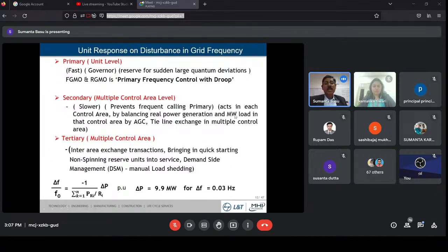So how can a very small frequency change demand a small incremental power? If there is a 0.03 hertz frequency deviation, there will be 9.9 megawatt. If we take a 660 megawatt generating station, and it experiences a 0.03 hertz frequency difference, it has to generate an additional 9.9 megawatt, or it has to lose this 10 megawatt of generation. The terminology used for this operation is free governor mode or restricted governor mode.